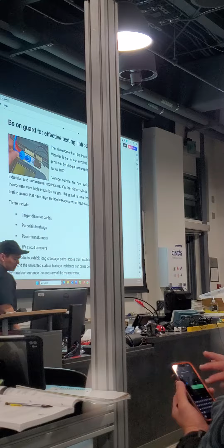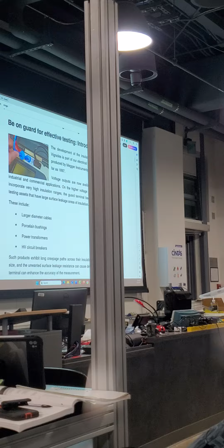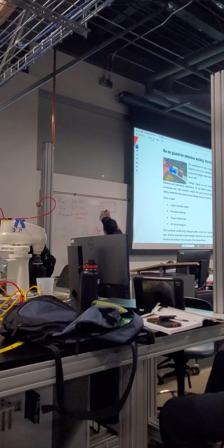So if I was to have another very helpful, awesome drawing. We'll have a cable here, we'll have our conductor coming out here. But if we anticipate that there's going to be an unintended path to ground, it may travel along here to the outside, and if there's a tape shield coming out, then it may pick up that unintended path to ground. This is going to look like breakdown, a short circuit, an abnormal condition.